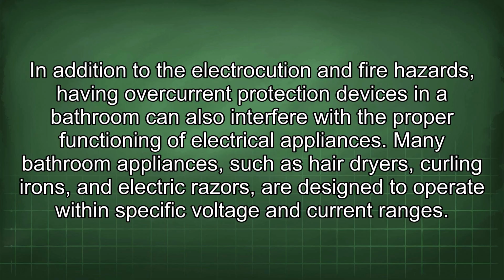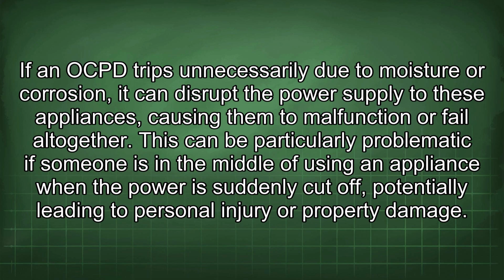In addition to the electrocution and fire hazards, having overcurrent protection devices in a bathroom can also interfere with the proper functioning of electrical appliances. Many bathroom appliances, such as hair dryers, curling irons, and electric razors, are designed to operate within specific voltage and current ranges. If an OCPD trips unnecessarily due to moisture or corrosion, it can disrupt the power supply to these appliances, causing them to malfunction or fail altogether. This can be particularly problematic if someone is in the middle of using an appliance when the power is suddenly cut off, potentially leading to personal injury or property damage.